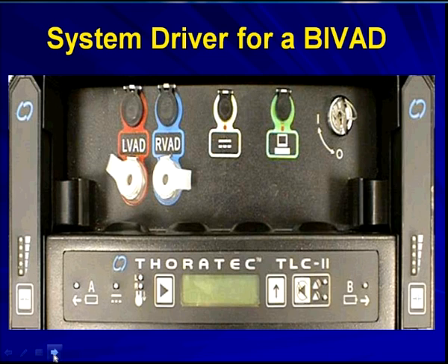So that's kind of an important thing. It's a bit overwhelming when you first look at it, but the key element is to know where those attachment points are, the LVAD and the RVAD, and, if it's pneumatically driven, to find out if there's a hand pump of some kind that goes with it. This particular one has two little blue bulbs, and those blue bulbs actually become essentially your chest compressions. So it's a very important take-home point.